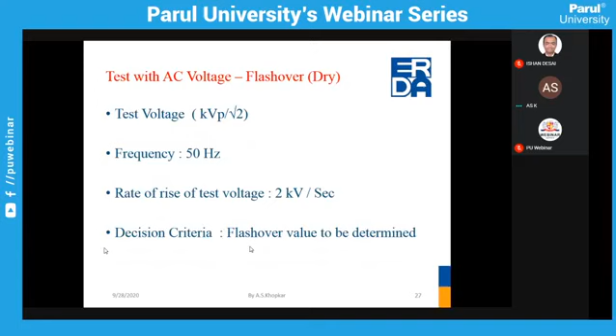In the case of transformers, CTs, PTs, this test is not applicable because insulators are self-restoring type insulation. So that is why this test is applicable on insulators only. If we perform such a test on a transformer, then the insulation provided inside the transformer, that paper insulation or oil, would get punctured, and then it is of no meaning. So that's why such a test is not applicable on the transformer. It is applicable only for insulators.